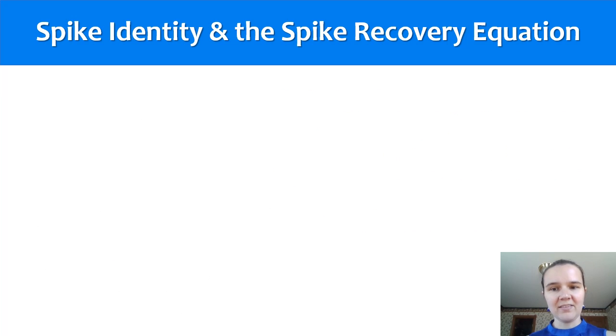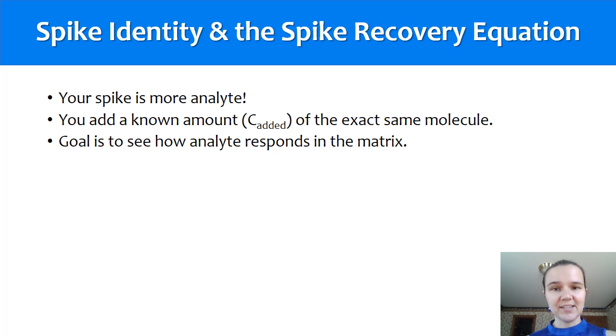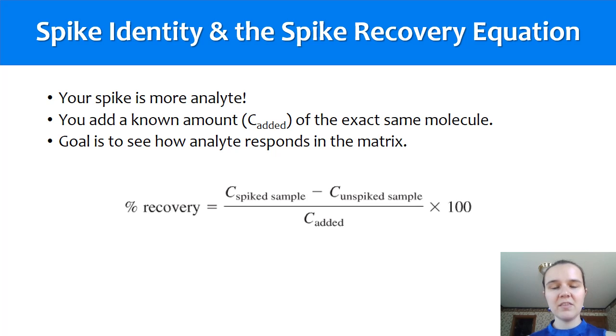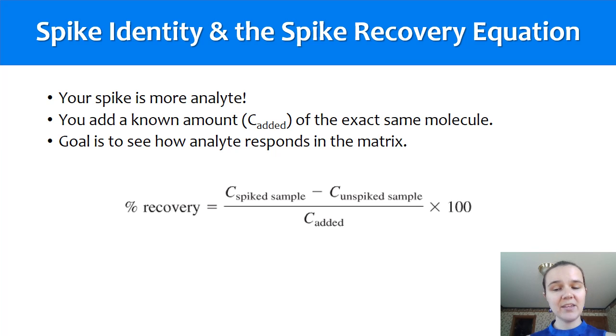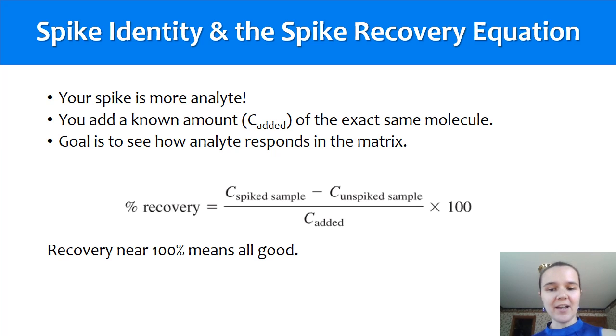The spike identity and the spike recovery equation: the spike is the analyte — you are using the exact same molecule as you're trying to analyze, and the goal overall is just to see how the analyte responds in the matrix of the sample. The equation for percent recovery is: the concentration of the spiked sample minus the concentration of the unspiked sample, over the amount that you added, times 100%. If all goes well you should get approximately 100% — you should measure as much as you put in.